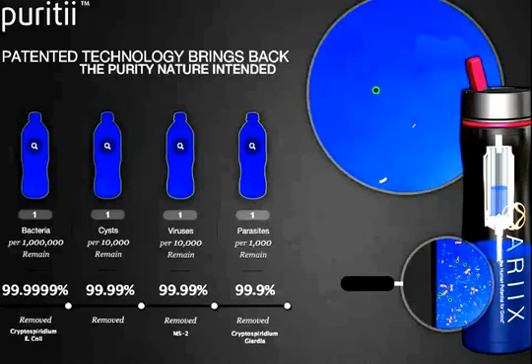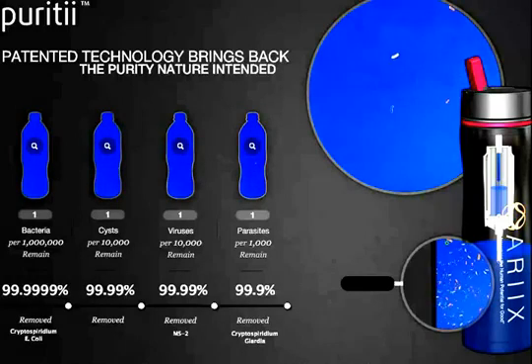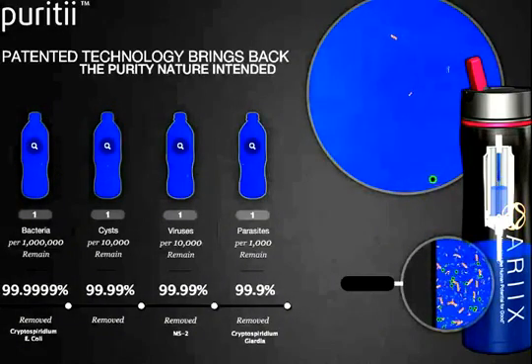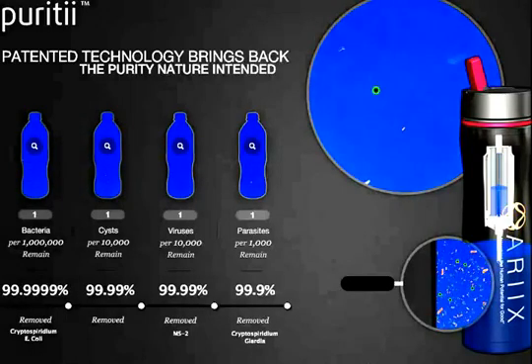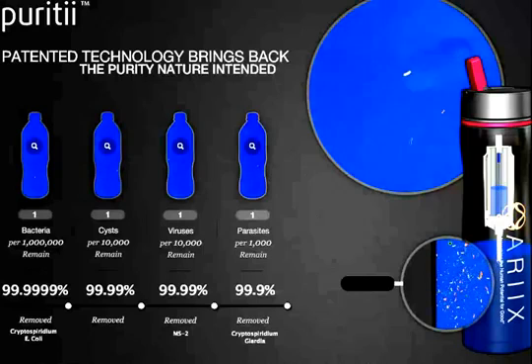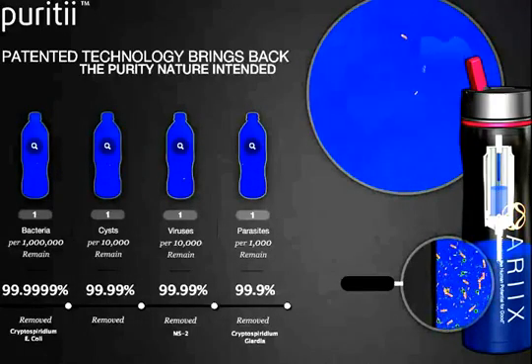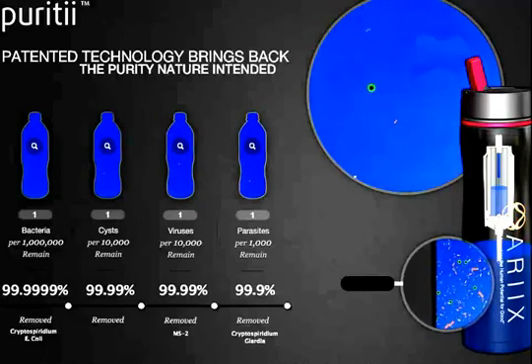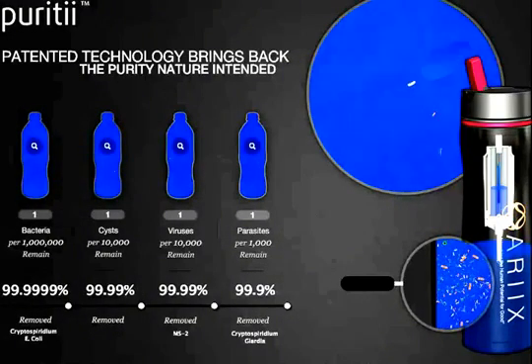This is very good. Inside this, the part that you can't see very well, is a pleated filter made from a revolutionary new material that is very exciting to me. It's a nano glass fiber — a very small fiber. The very small fiber is also surface treated with what's called a high zeta treatment. A high zeta simply means that it has a very strong electropositive charge. Most organisms that you will find have a negative charge, an actual negative charge. And so the high zeta material works like a magnet and actually pulls the contaminants out of the stream.